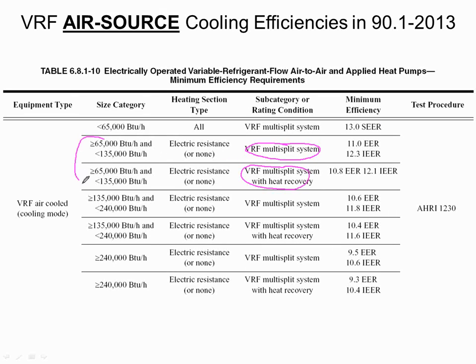And that's for each BTU range. You'll have one and the other. Right? And in the next BTU range, he'll have both regular and heat recovery. And the next one, regular and heat recovery. You will note in general that if you have heat recovery, your EER and IEER numbers get slightly less for having heat recovery.